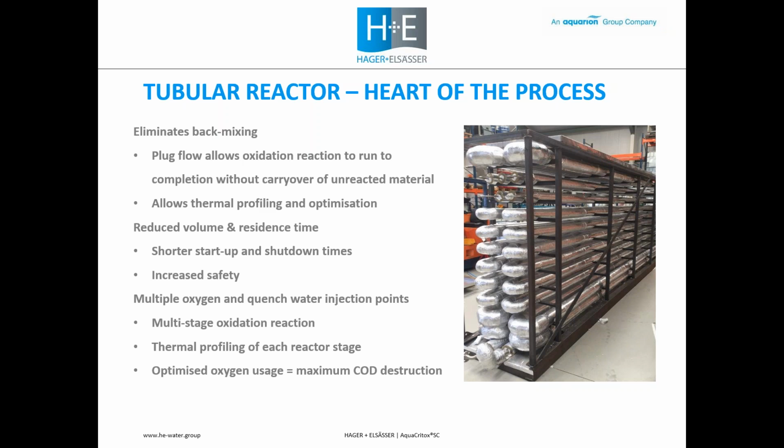Also, the use of a tubular reactor over a standard vessel allows us to reduce our retention times. So our total retention time is only 12 minutes for this system. It increases safety. It means that we can use a much thinner walled system and maintain the same levels of integrity even with the smaller volumes and the smaller pipe sizes. A large pressure vessel inherently has very thick walls. They're heavy and they're cumbersome, and the performance that we can achieve cannot be achieved in the same way.